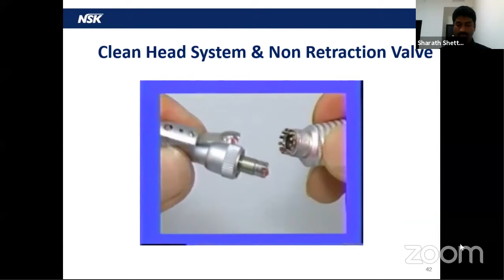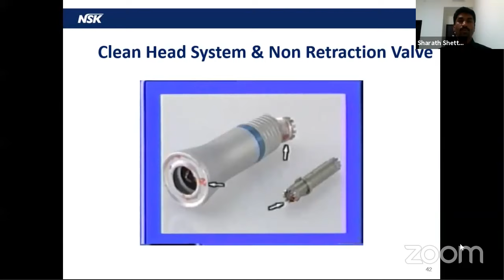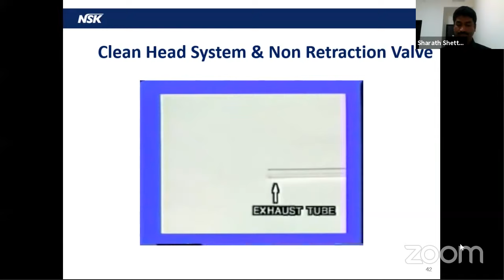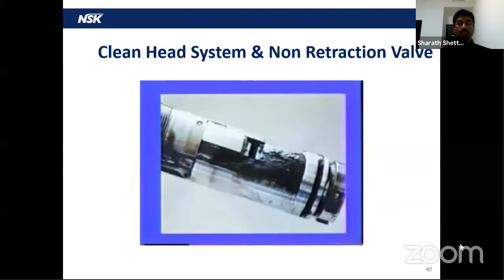Those that penetrated into the air turbine of the handpiece are discharged at the back end of the handpiece into the atmosphere or into the dental units with the exhaust air. These foreign matters are floating into your dental office, and all of you are exposed to them. The foreign matters that remain in the handpiece just accumulate in it and are baked after repeated autoclaving. They may cause troubles or shorten the instrument life.